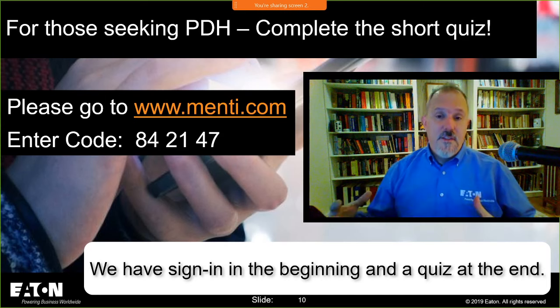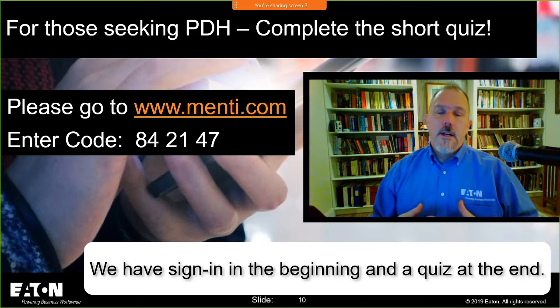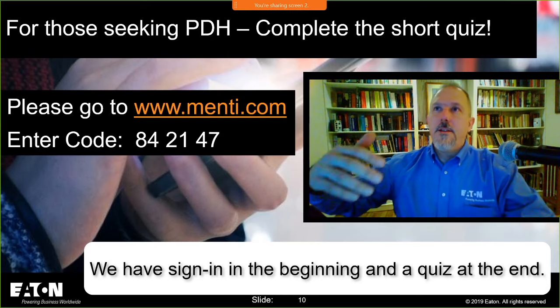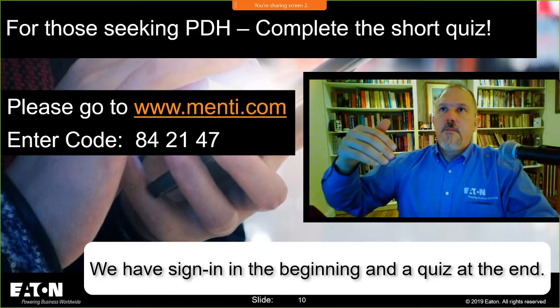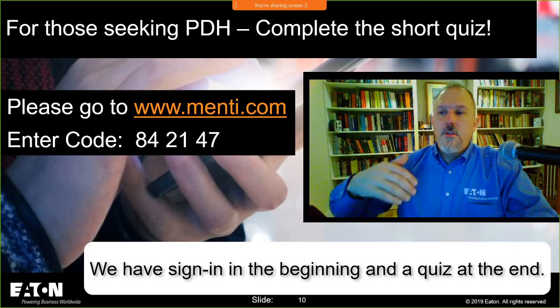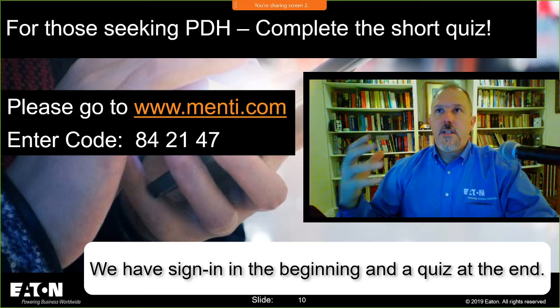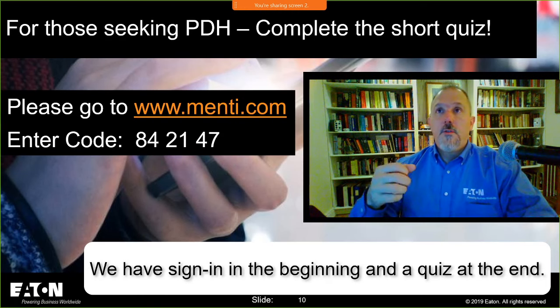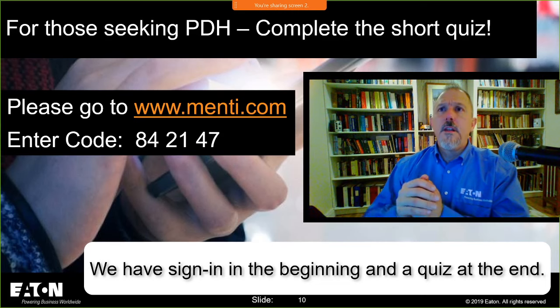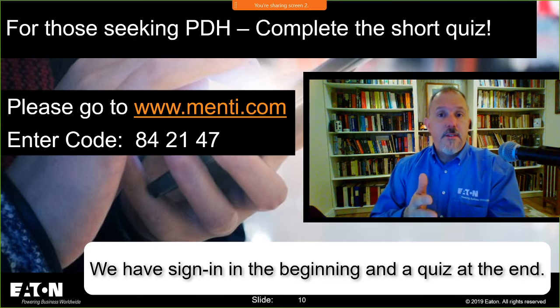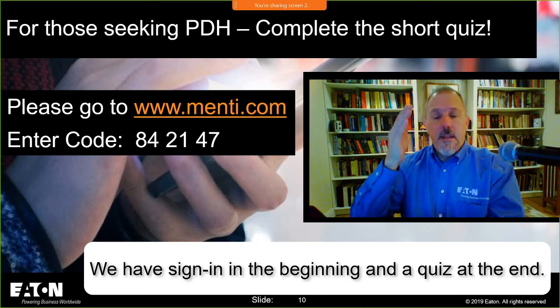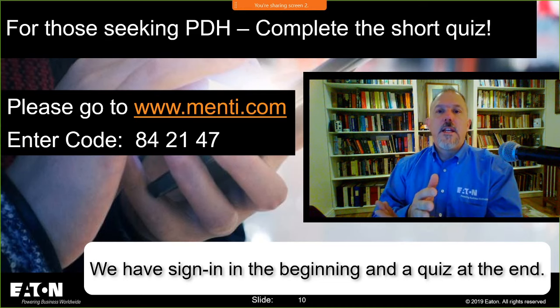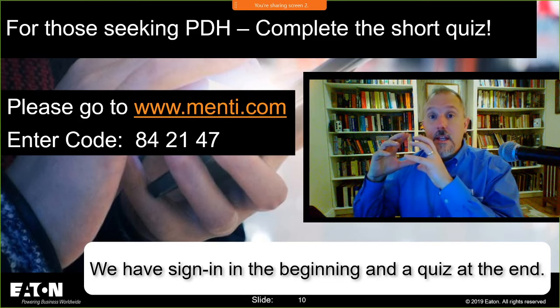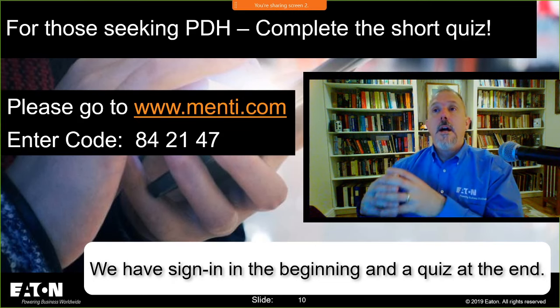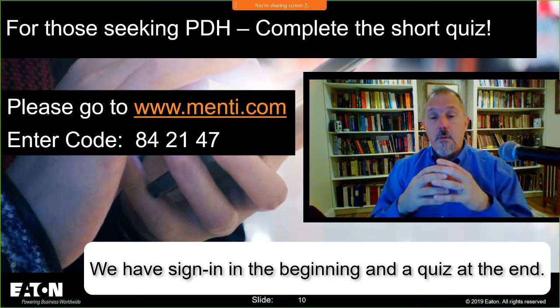So here's what we do in the design phase. I don't know if you're the engineer or you're the inspector, but if you're the inspector, you want to communicate with the engineering firm to say, look, you've got to make sure that if it's an Article 700 system, then you're going to want to selectively coordinate. And get them to tell you what level of coordination they're going to provide. If it's a 700, it's got to be selective coordination all occurrence all times. Get them to check that box and sign off and say that's what they're going to get you. And now that's part of the record, and that's in the design engineer's mind that that's what he has to meet, and then he will approach it appropriately.